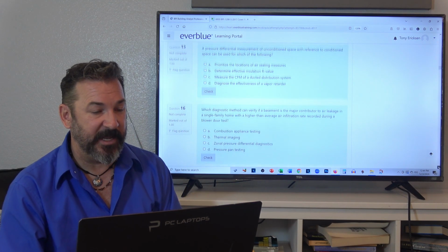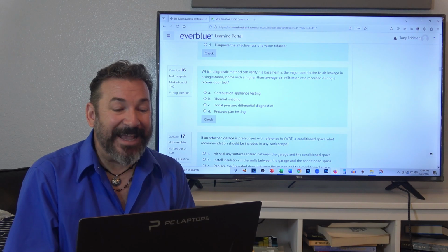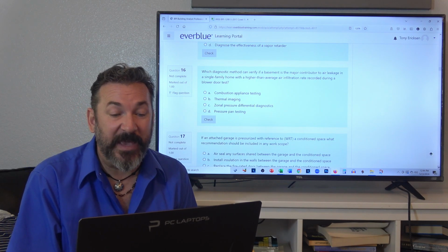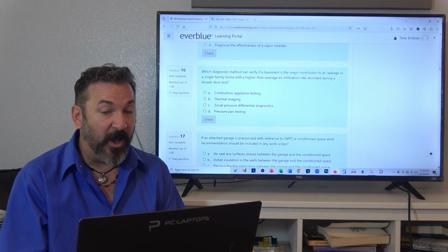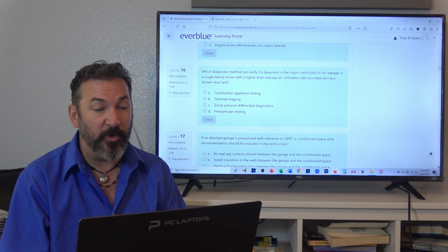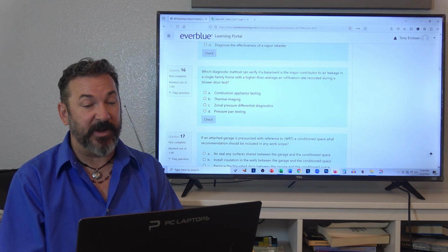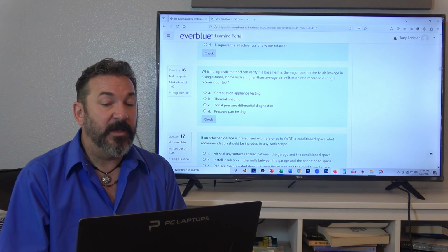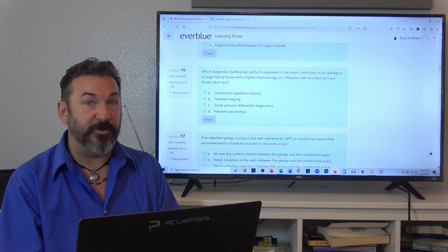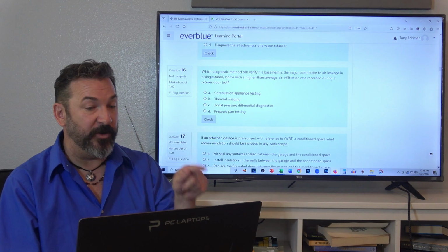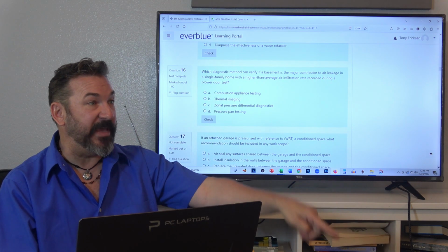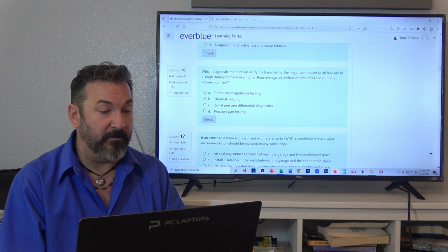Okay, 16. Which diagnostic method can verify if a basement is the major contributor of air leakage in a single-family home with higher than average air infiltration rate? So it's a very leaky house. Recorded during the blower door test. So you're doing a blower door test. What can we do to verify that that basement is leaky?